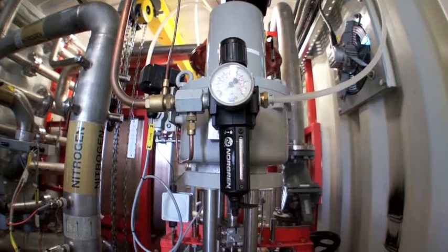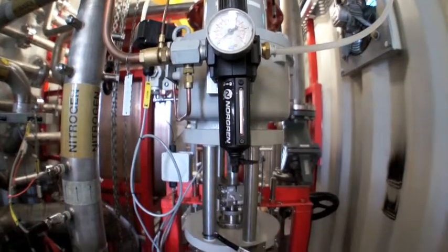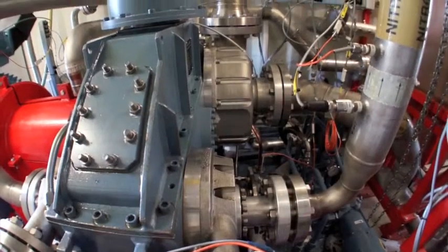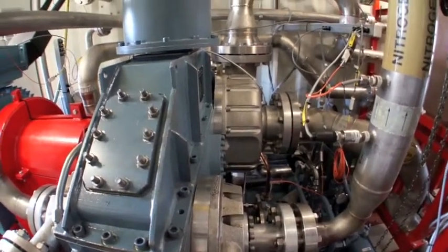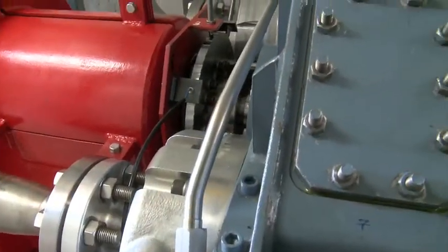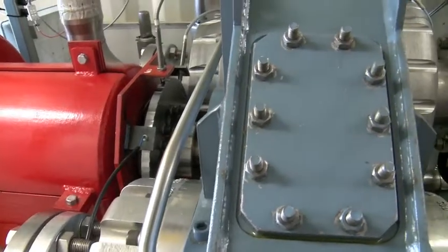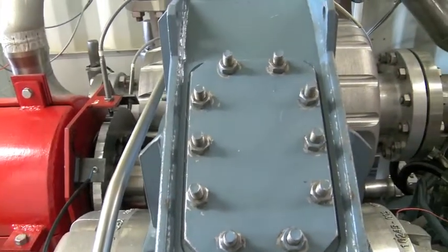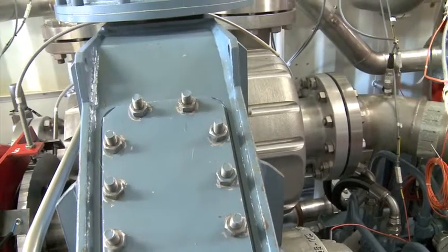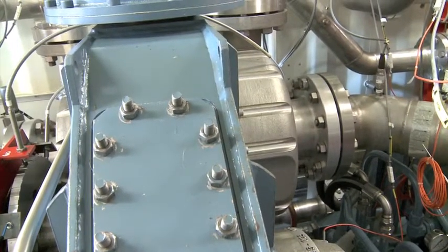Here's our high pressure thousand pounds per square inch gas. It comes through the control valve which controls the power output. There are four turbines going from small with high pressure, gradually getting larger and larger until you get to the final stage at its lowest pressure. When the gas goes through the turbine it goes in at ambient temperature but it drops in temperature as it gives up its power to the turbine.